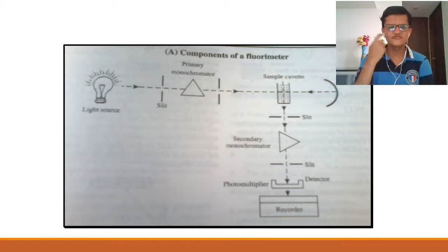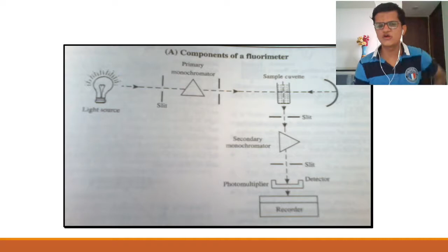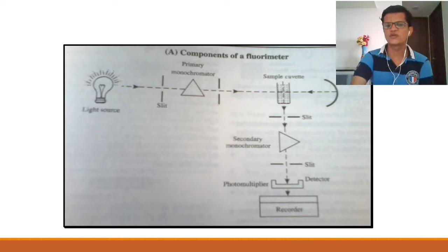The light source generally used is again a xenon arc lamp, or a mercury vapor lamp, or a hydrogen discharge lamp. The primary monochromator can be a grating or a prism. Sample cuvettes, and again an emission monochromator. In this case, you need two monochromators, because the sample molecules also emit light. So, to again convert that light into monochromatic light, you need a monochromator. And last is the photomultiplier tube, or detector.